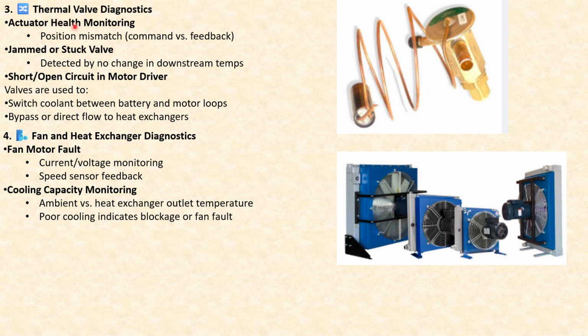Now, when it comes to thermal valve diagnostics, first is the actuator health monitoring, whether the position mismatch needs to be monitored very thoroughly. Okay, the command versus feedback, whether it is working properly or not, must be, I emphasize the word, must be thoroughly monitored. And next is jammed or stuck valve, detected by no change in downstream temperatures. Now, when it comes to short or open circuit in motor driver, valves are used to switch coolant between battery and motor loops, bypass or direct flow to heat exchangers.